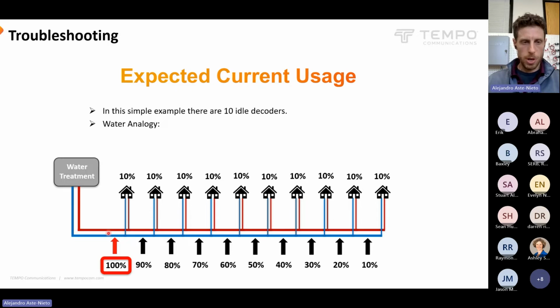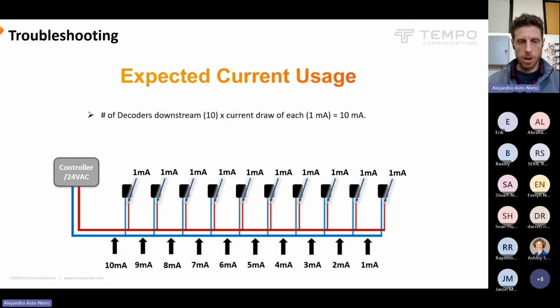So again, here is where 100% of the water servicing these houses will be flowing, whereas here it's going to be half. So to put this in terms of real world numbers, let's say each of these decoders uses 1 milliamp to make it easy. If you take a clamp meter reading here, you're going to see 5 milliamps. If you take a clamp meter reading here, you're going to see 10. Each of these decoders uses 1 milliamp, 10 decoders, we've got 10 milliamps here.